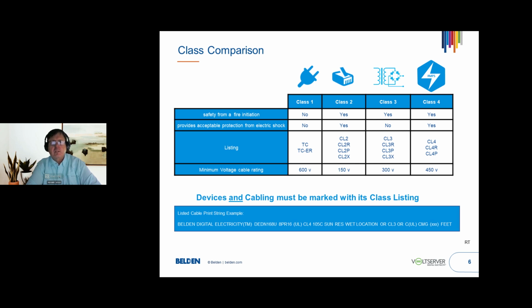But if you look on the technical data sheets for those cables, you will see what the cable voltage rating is. Please note, a PoE cable, which is typically our category cable, usually has a 300 volt rating. Some might have less, but the Class 4 cable has a 450 volt rating. So it's really important to know that, because you can't just use category cabling for this powering in most cases.